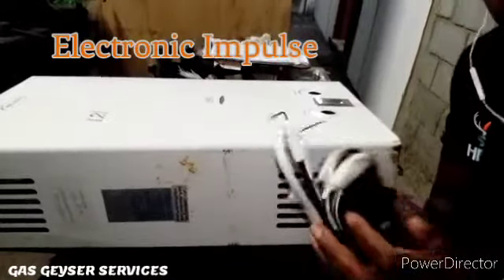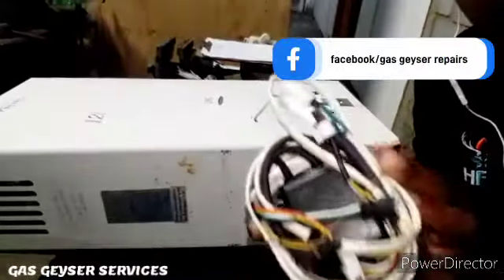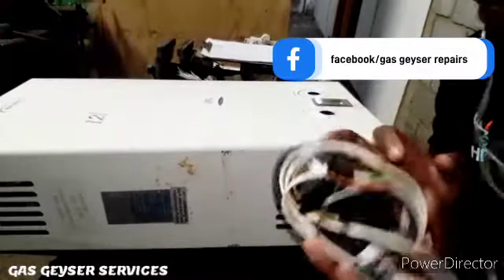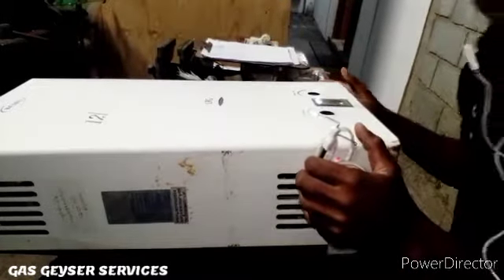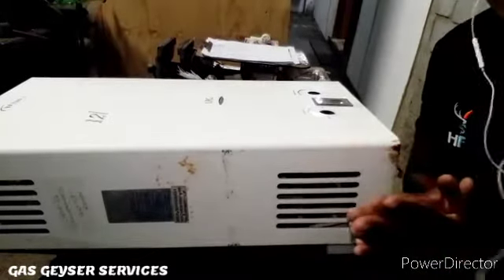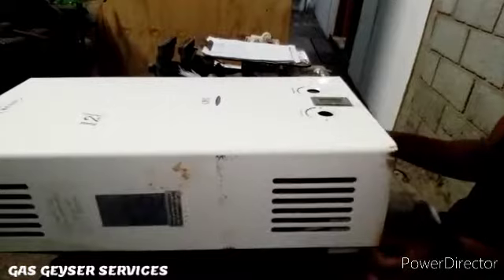Hi there guys, for this video we're going to be installing a brand new control box, which is a electronic impulse for a gas geyser for the ignition. We're going to be taking this control box and installing it inside this unit. The problem with this unit is it's not sparking, so it's not igniting at all, so we're going to replace it and put a new one on. Let's get to it.